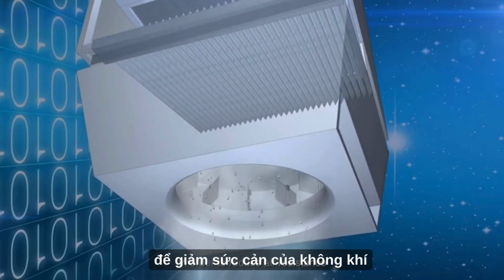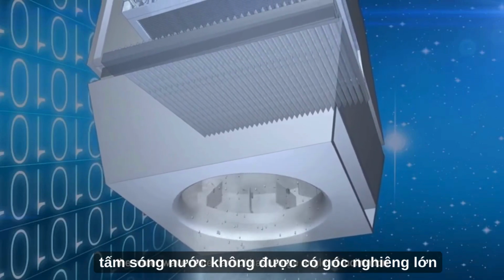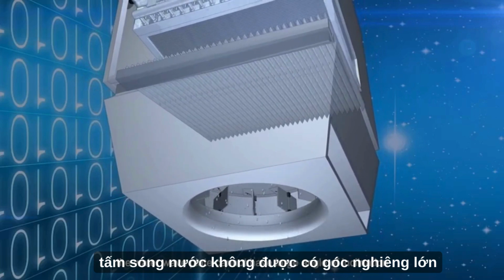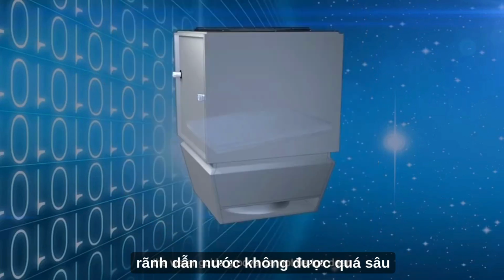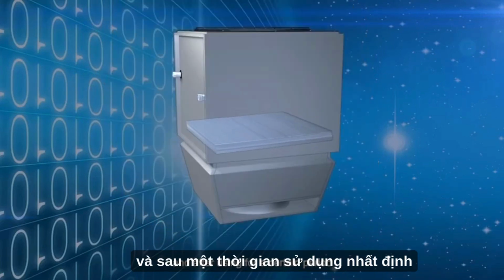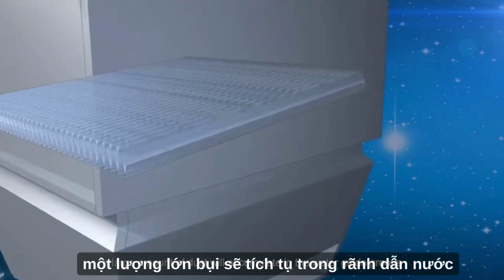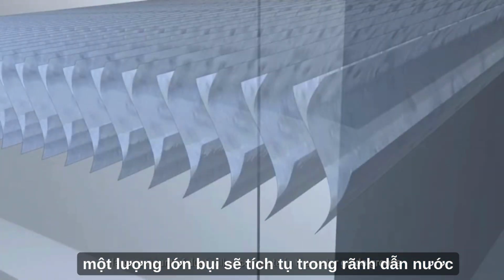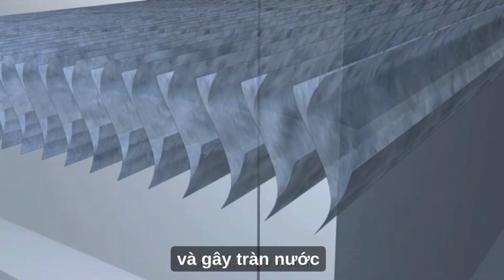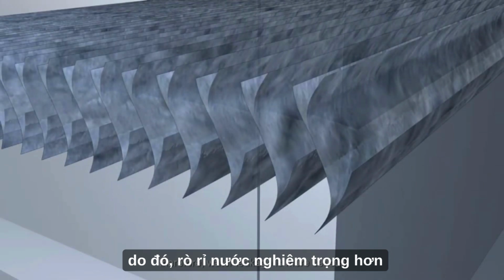In order to reduce air resistance, the water wave plate cannot have large angle of inclination. The water guide groove cannot be too deep. And after using for a certain period, a large amount of dust will accumulate in the water guide groove and cause water overflow. Therefore, water leakage is more serious.